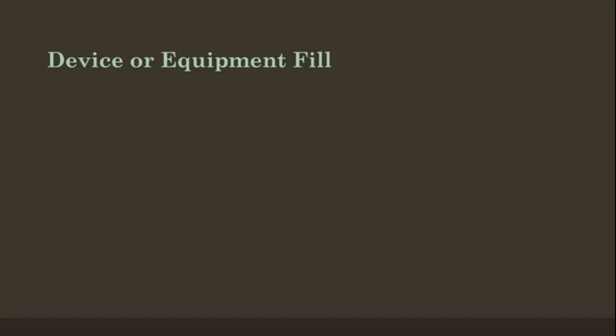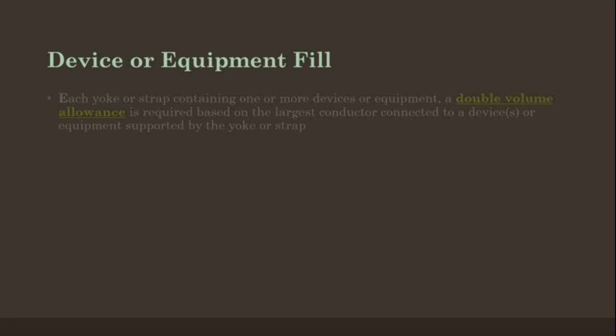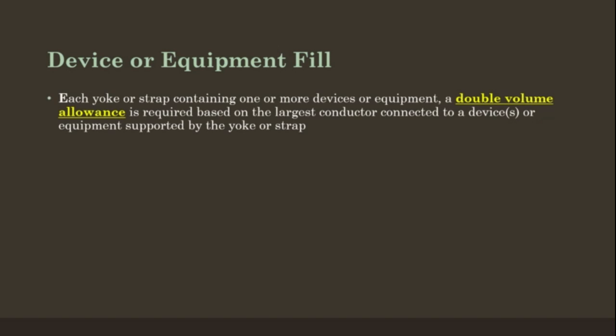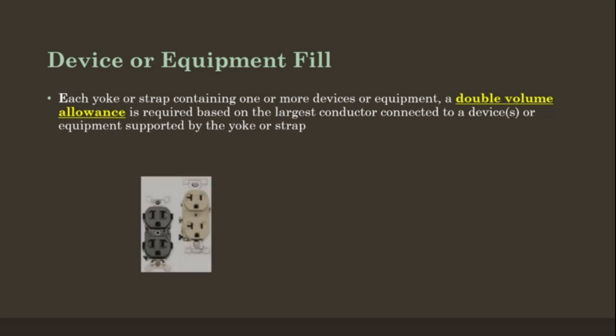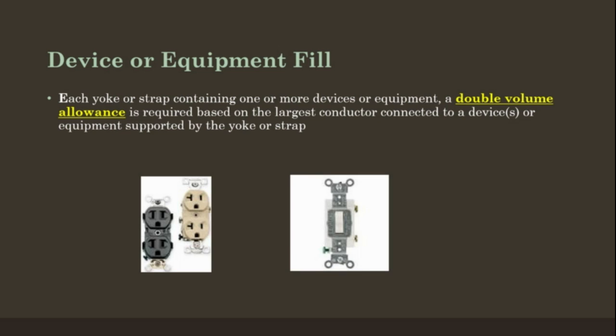Device or Equipment Fill. Each yoke or strap containing one or more devices or equipment, a double volume allowance is required based on the largest conductor connected to the device or the equipment supported by the yoke or strap. See the examples below.